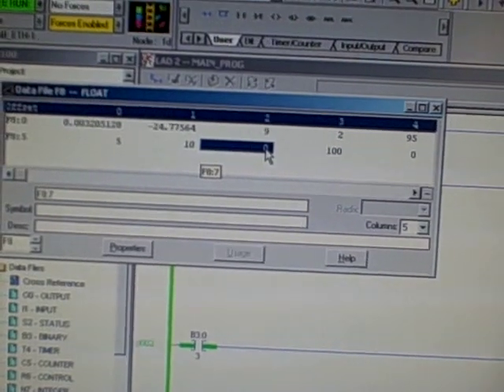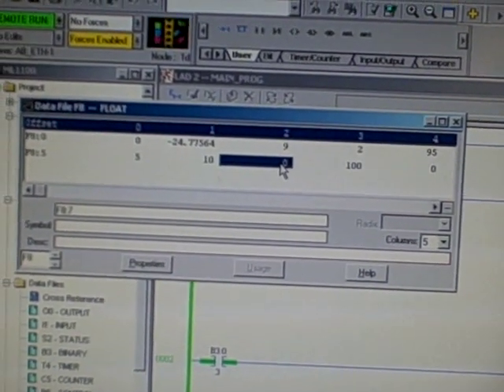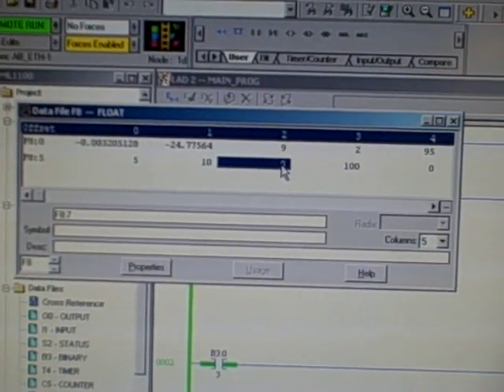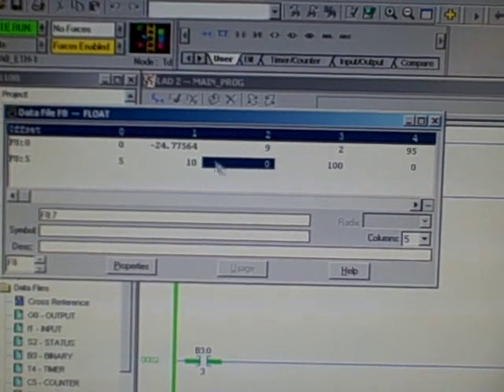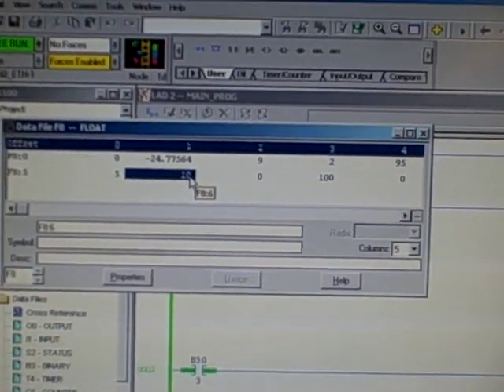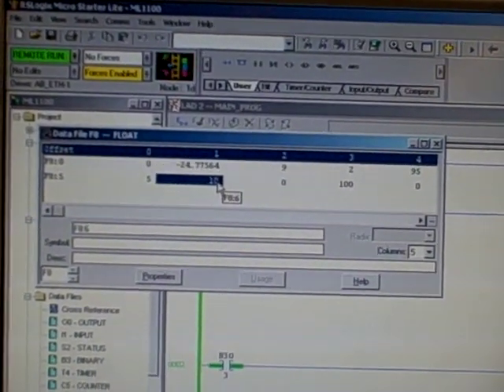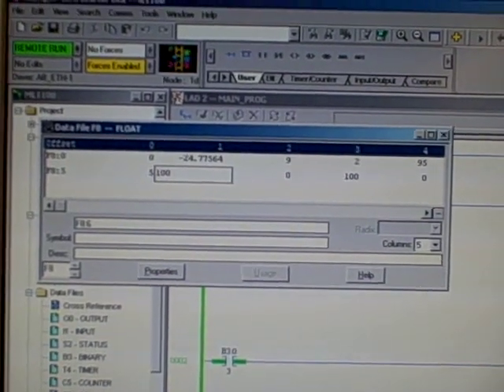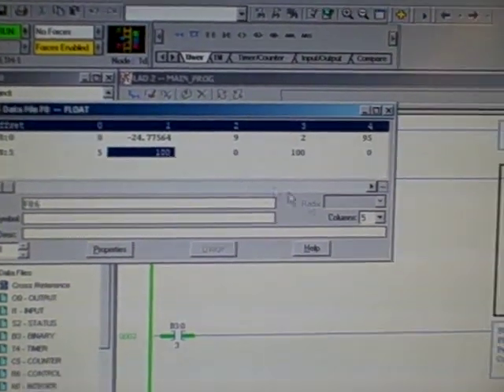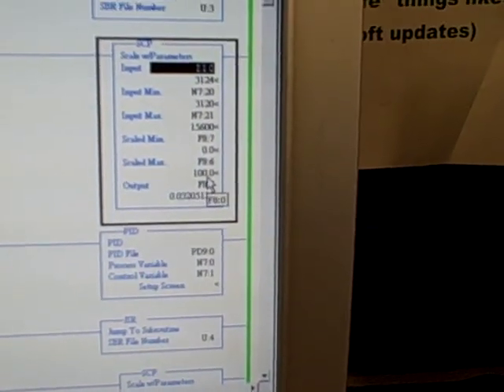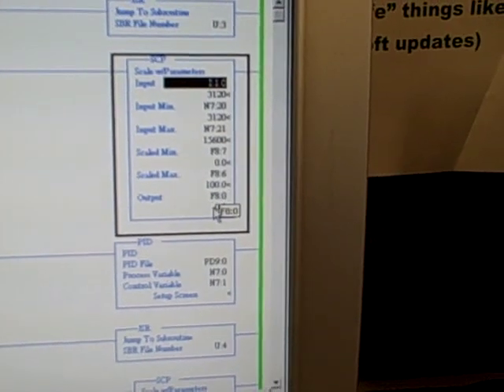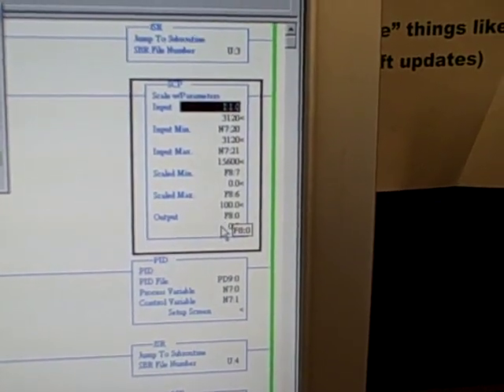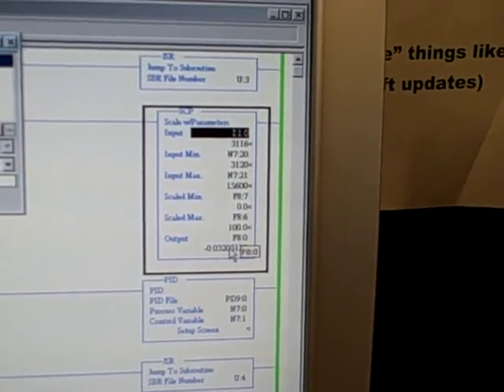So let's suppose we wanted this to express the process variable in terms of percent instead of PSI. I could simply change that to 100, representing 100%. I hit the enter button, and as soon as I do that, you see that number value updated there, and lo and behold, we're going to be scaled in percent here instead of PSI.